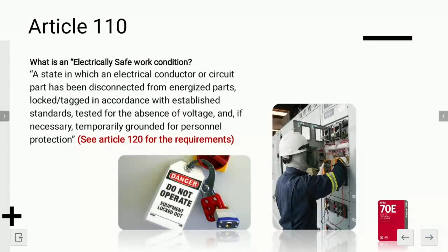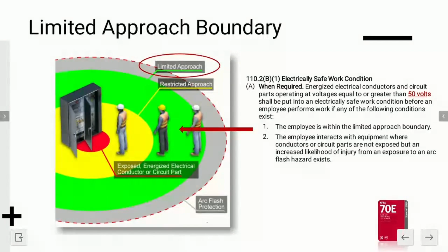So what's the limited approach boundary? Now, I know we don't have a whole lot of time today, but here are your boundaries. These are the approach boundaries that Dev was asking about. I got you, Dev. Okay. Now we have 3 boundaries. We have what's called an arc flash boundary. It's a red dotted line. And then we have what's called the limited approach boundary and restricted approach boundary. Those are the 3 approach boundaries we have to maintain if we're allowed to be exposed to 50 volts or higher.